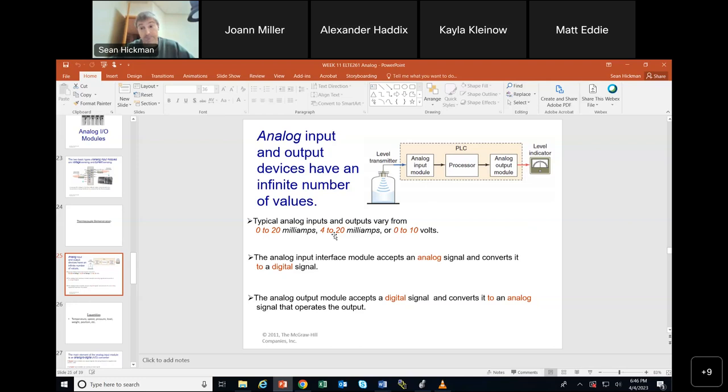All right, 8.63. And if you have the resolution set, then you can convert that to something. Like I showed you with the resolution, our units are set up to be pretty high resolution. Or you could have a value coming in of 8.63 volts, and that would mean something, okay? There are other ones you could use here, but I mostly see 4 to 20 milliamp sensors and 0 to 10 volt sensors. Does anybody see anything different at work? Any kind of analog sensors, anything different than that? 4 to 20s or 0 to 10s is what you would typically see for your analog sensors, all right?